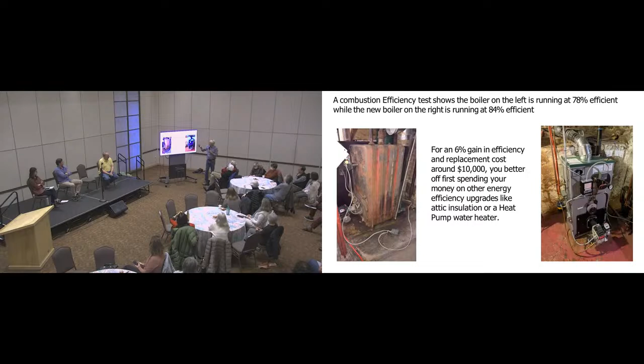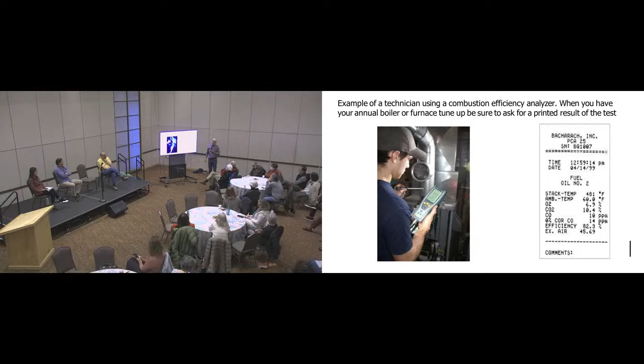This is a combustion efficiency tool. Every year you probably have your boilers tuned up—the oil company comes out and does things—but a lot of times the technicians won't use this at all. They just do everything by eye, and they can get it close, but I'd encourage you to insist that the technician does a combustion efficiency test and gives you this little printout. It tells you how it's doing. If the technician says, oh, I don't need that thing, say, I don't need you, and ask for a different one. You can see here the efficiency of this boiler was 82.3%. If you got one of these and it said it was running at 72%, something's wrong—usually it's a matter of internal cleaning of soot and things like that. So this little report the machine spits out is very important.